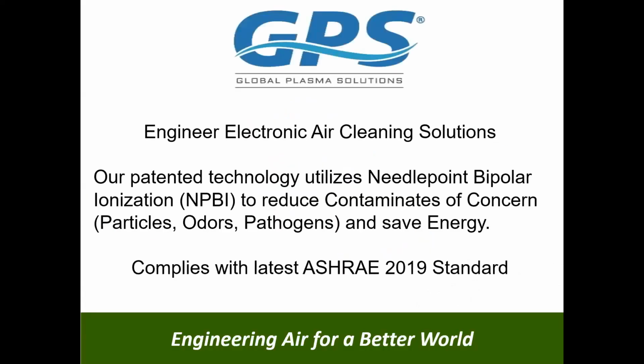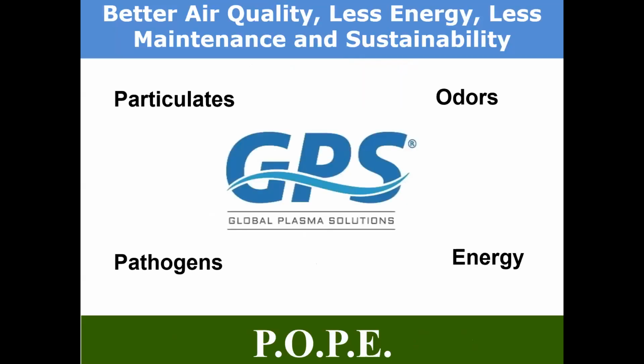But we basically engineer electronic air cleaning solutions, and we do it using needlepoint bipolar ionization, which we'll talk about. And we do that to reduce the contaminants of concern, and those are really particulates, odors, and pathogens. And we call that POPE. And the last, the E, is the same as Ivan said. By using ASHRAE 62.1, we can lower outside air if you can clean the air of the contaminants of concern.